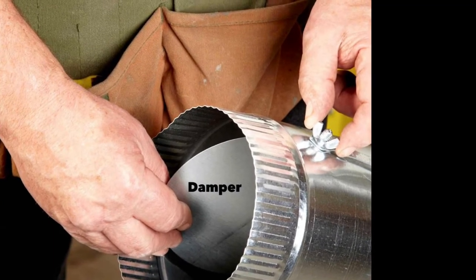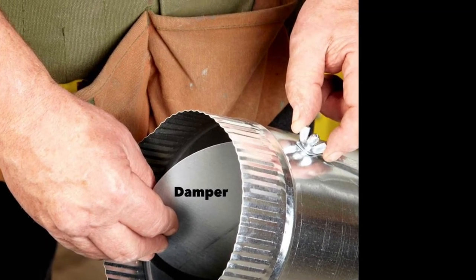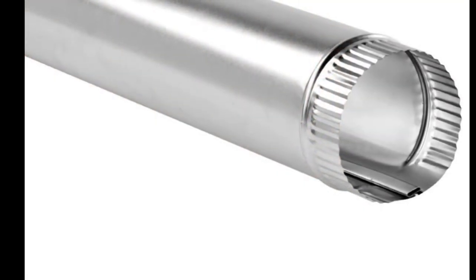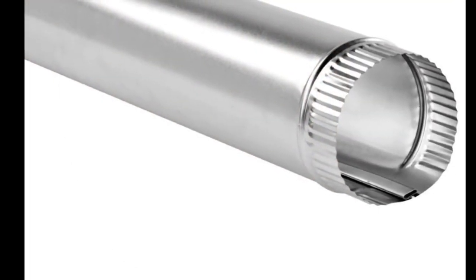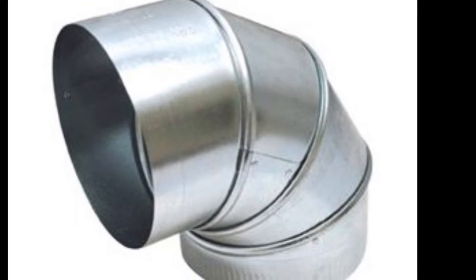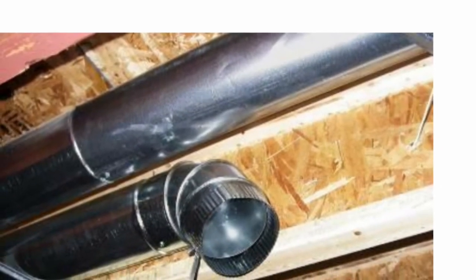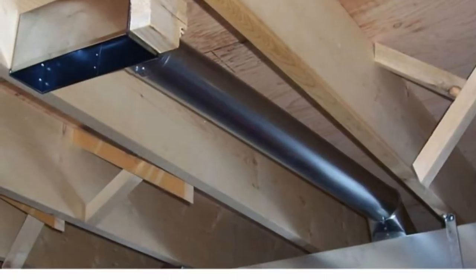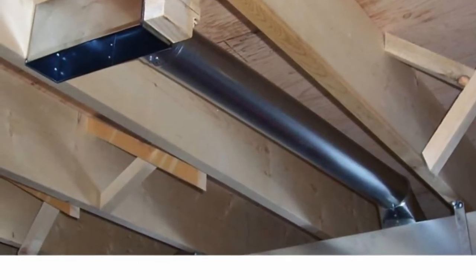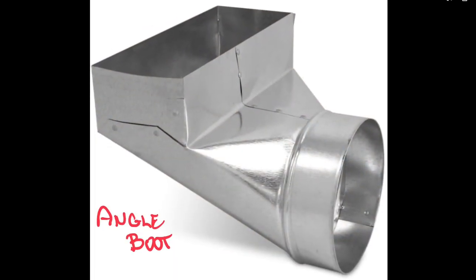After a takeoff, if possible, install a balancing damper into the pipe, which is called the branch. And most of the branches will require a few elbows. The very last fitting on every branch is called a boot. There are three types of boots.